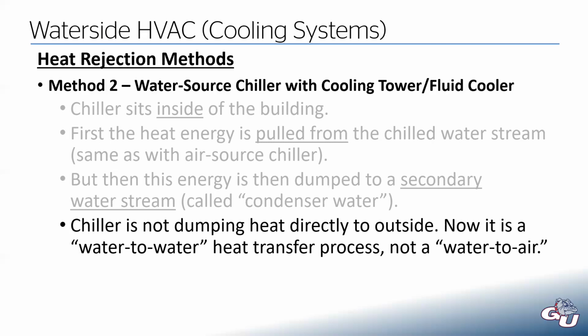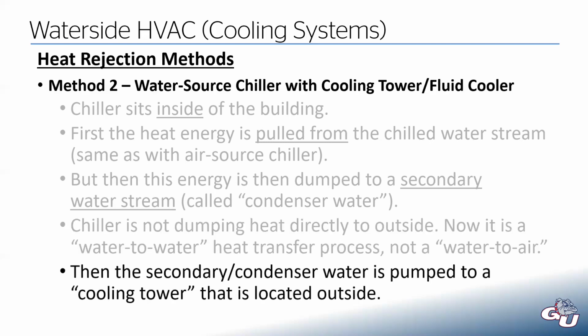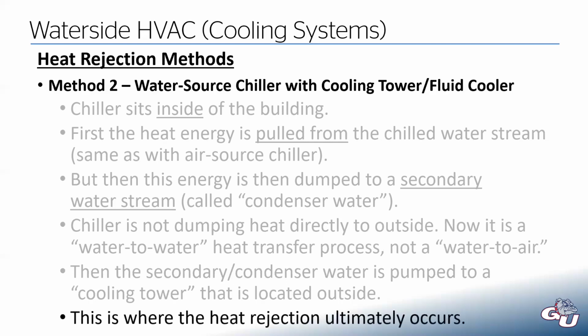We're still using a DX refrigeration cycle. It's just now we're moving energy from a water stream to another water stream. Then that secondary condenser water stream is pumped out to a cooling tower or a fluid cooler that is located outside. We still have a device that's outside. It's just that it is now our cooling tower instead of our chiller. And that is where our heat rejection ultimately is going to happen.